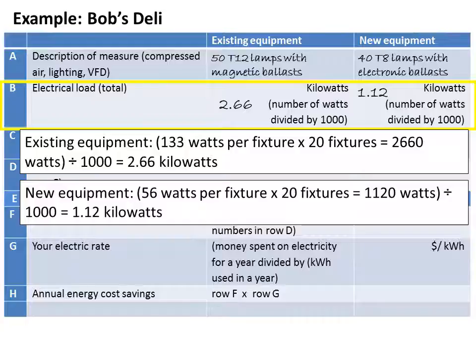Bob is replacing 20 fixtures. Therefore, to get the total electrical load for all 20 fixtures, Bob multiplies the 133 watts per fixture by the number of fixtures, which is 20. The result is 2660 watts, which he divides by 1000 to get 2.66 kilowatts. Bob made the same calculations for the new equipment and determined the electrical load for the new equipment is 1.12 kilowatts.